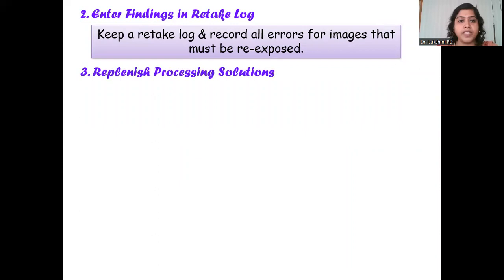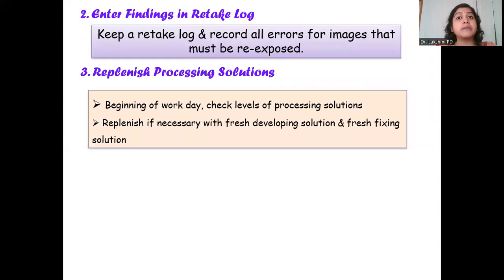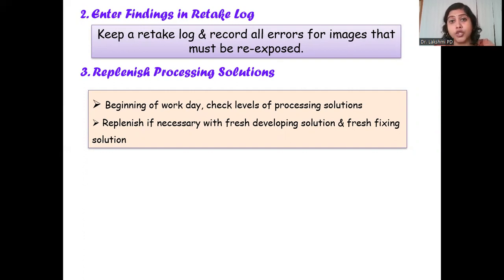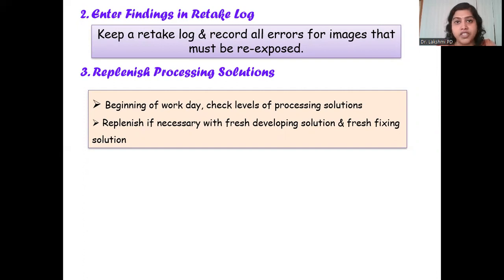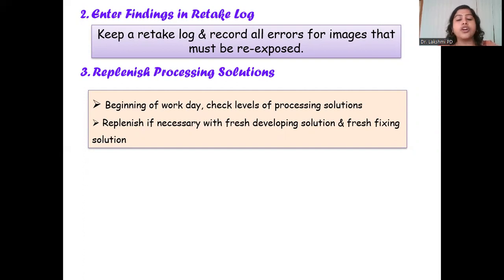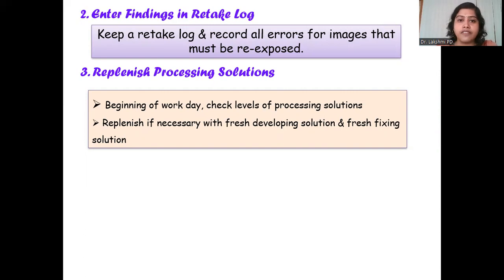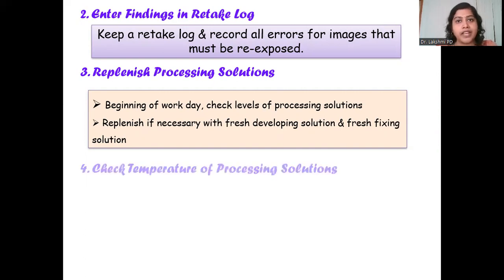The third daily task is replenishing the processing solution. You do not replenish your processing solutions every day; rather, check the levels at the beginning of your work day. If the developer and fixer levels are towards the bottom of the tank, replenish them that day. Keep in mind that if the fixer is low, you change both your developer and fixer solution. Always change both together, mixing them according to the manufacturer's instructions.